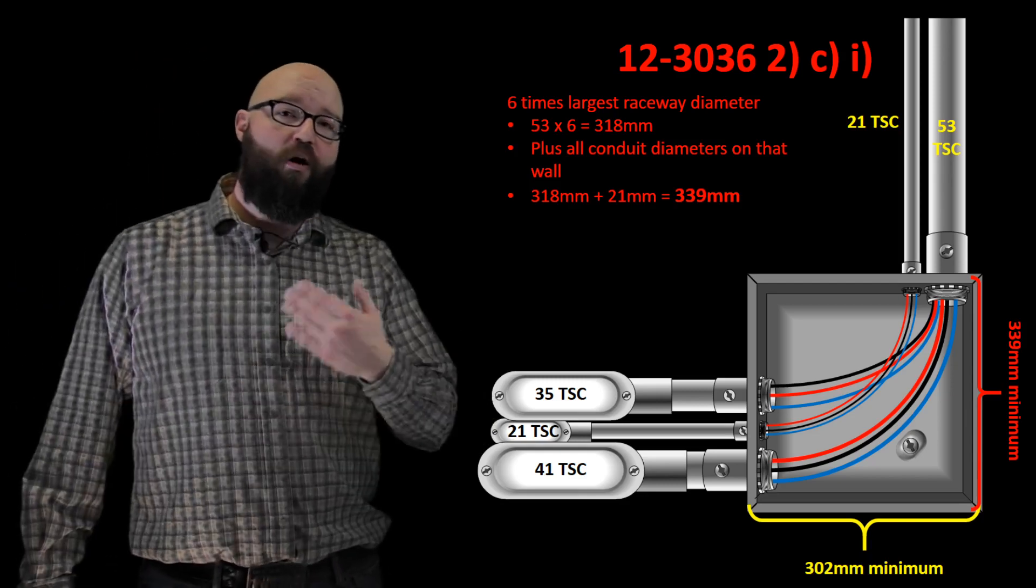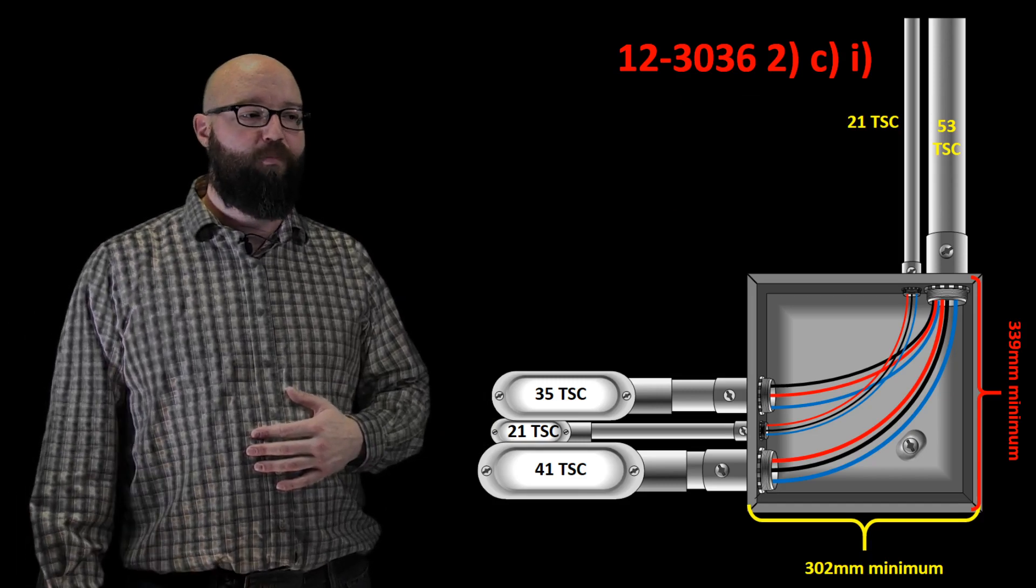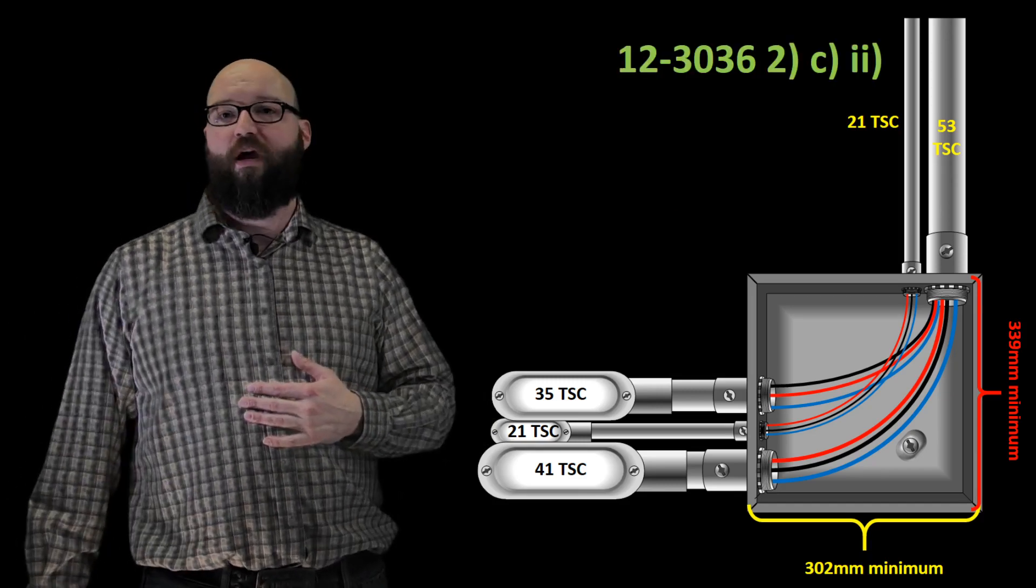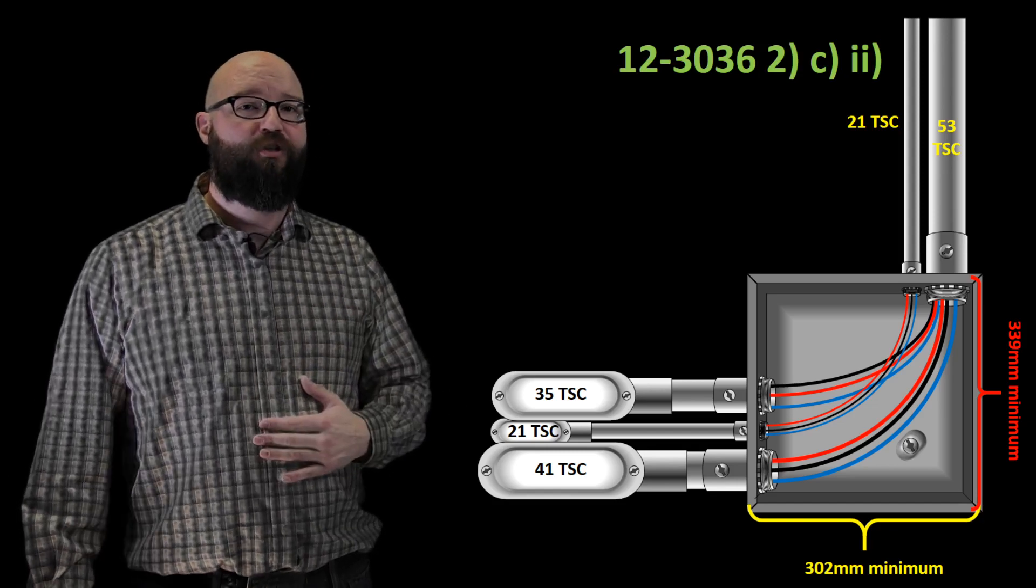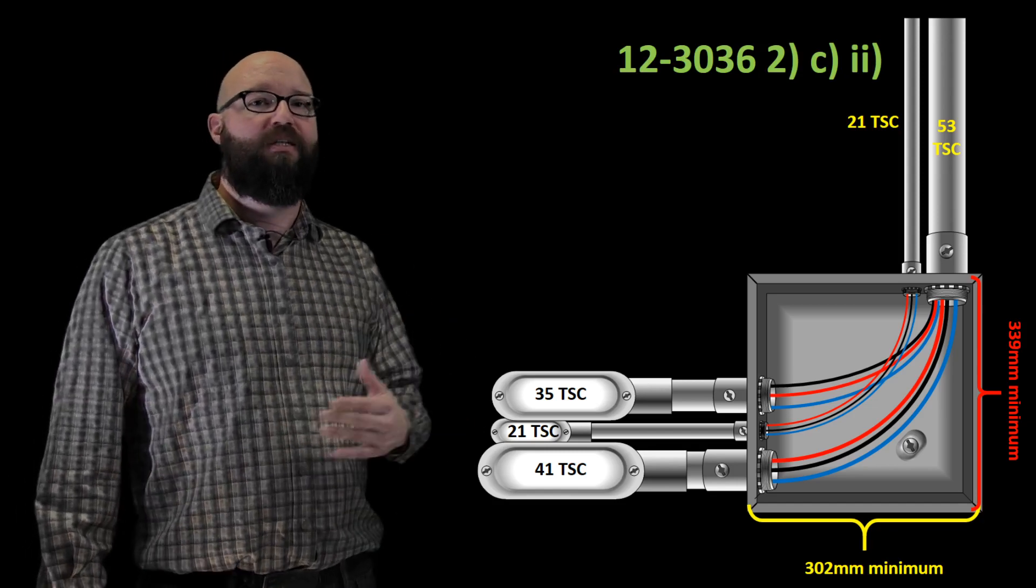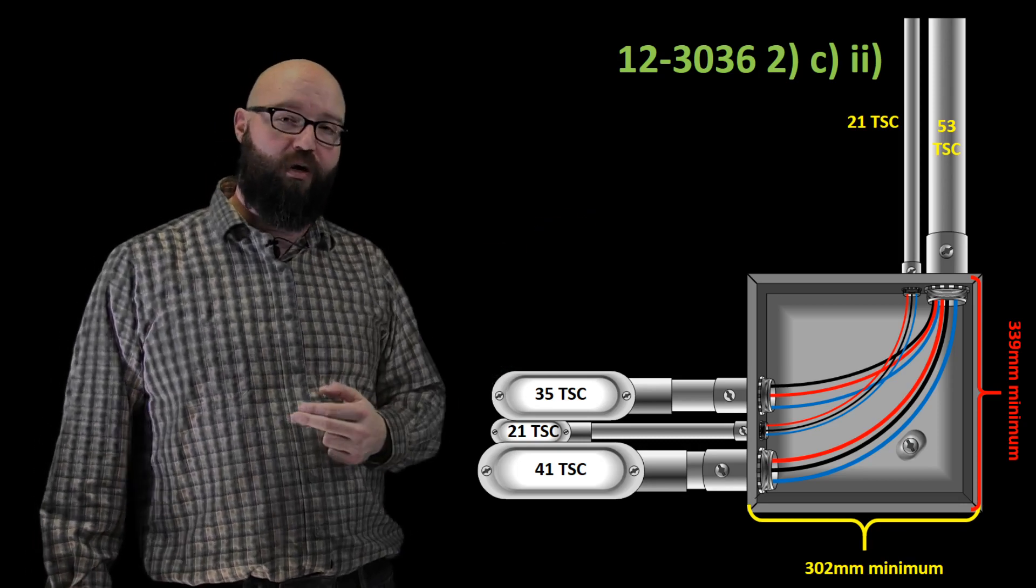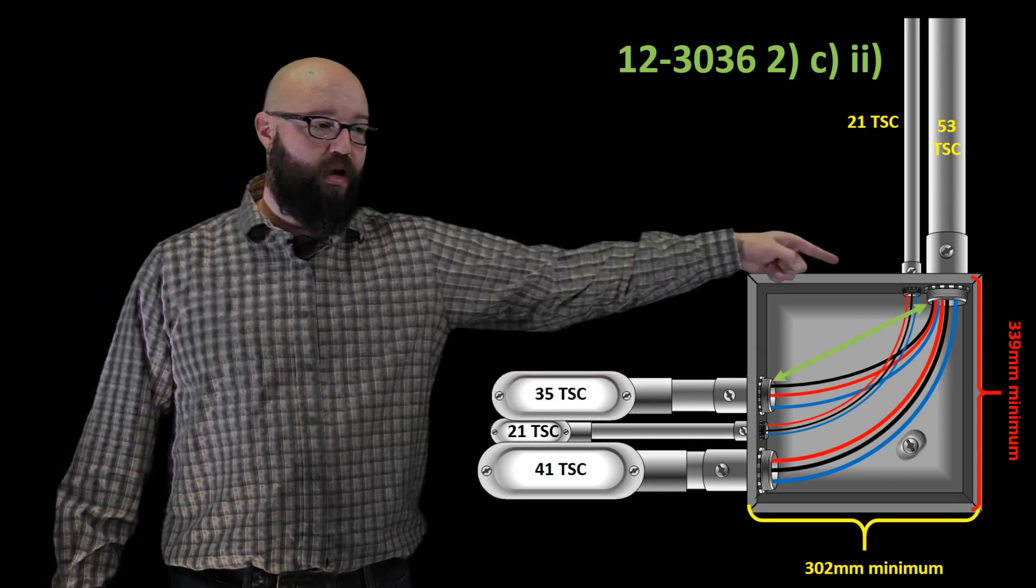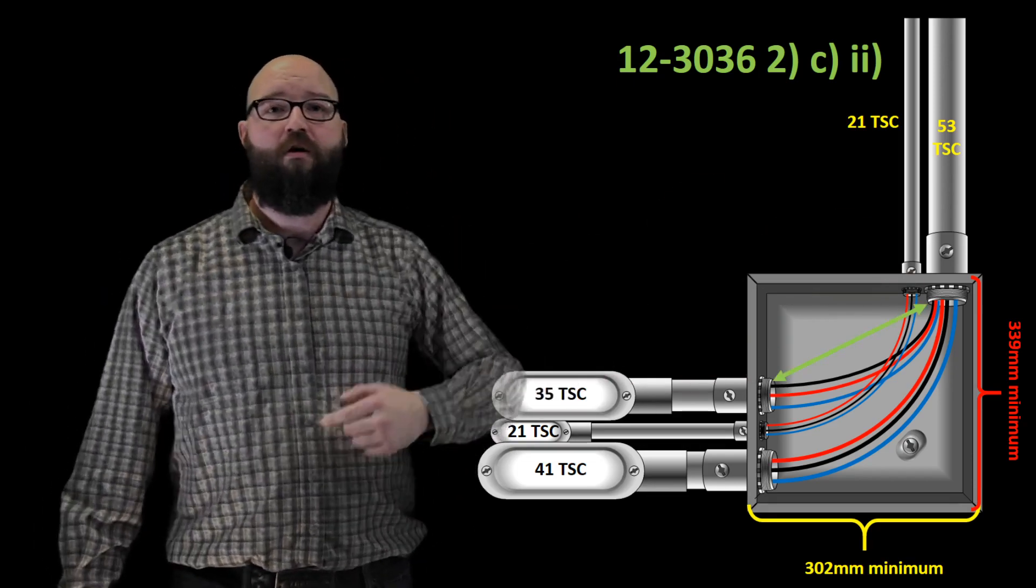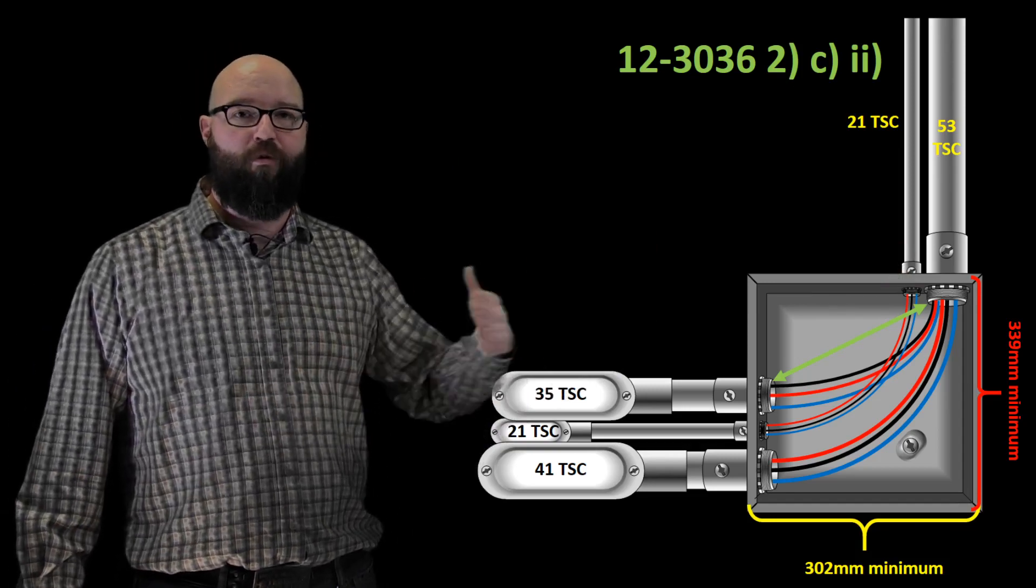So there are two other dimensions that we have to take into account when we are doing a pull box like this, especially an angle pull. We have to take into account 12-3036 sub rule 2 item C-II, which actually tells me what the minimum distance is between two conduits that contain the same conductor. So in this case, these two conduits right here, we have this one and where it enters over here, we need to figure out what the minimum distance is between those two on the innermost points.